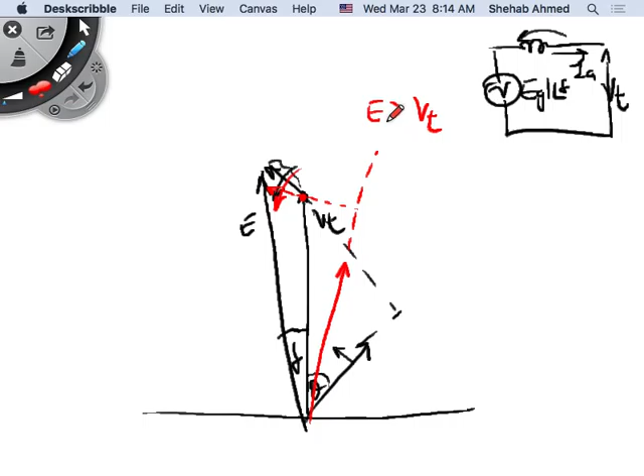So this remains the lagging power factor case. The characteristic you'll notice is that E will always be greater than VT in the lagging power factor scenario, and that's where the generator's AVR performs its function.